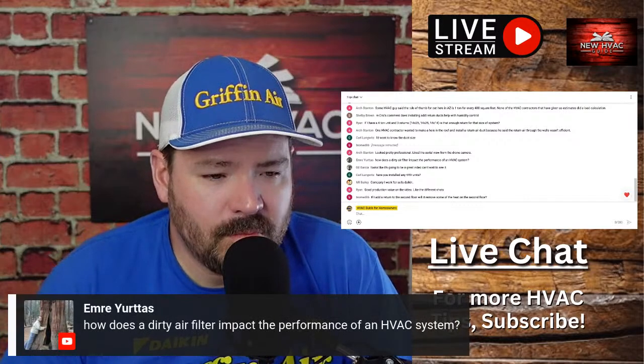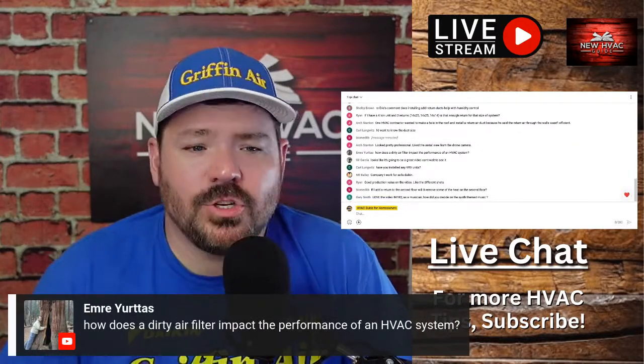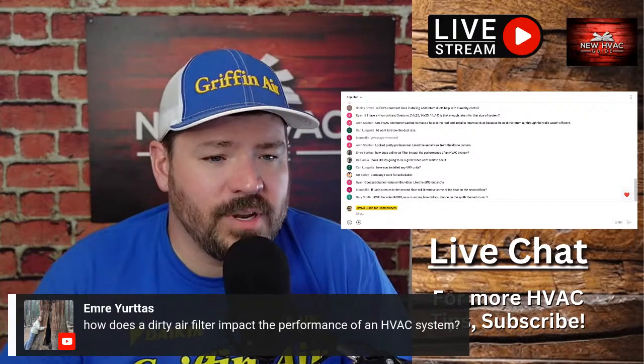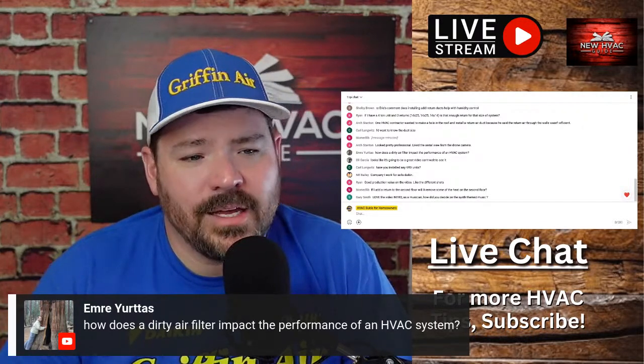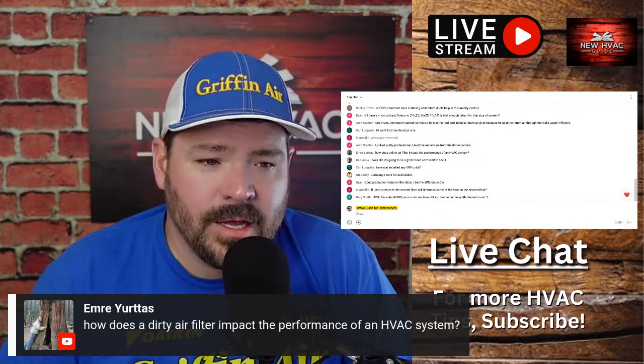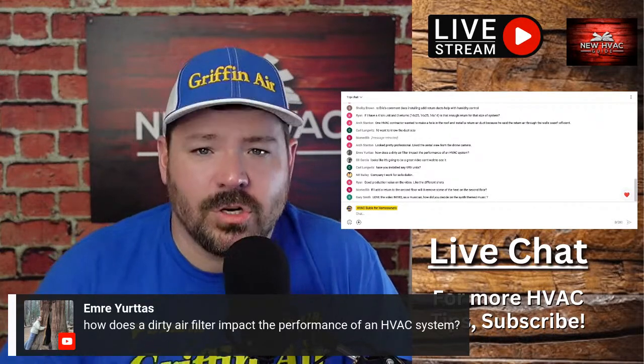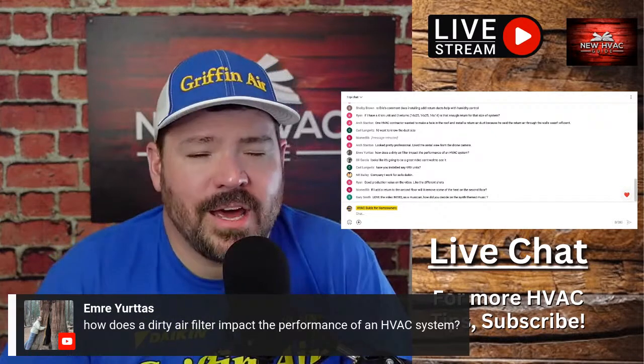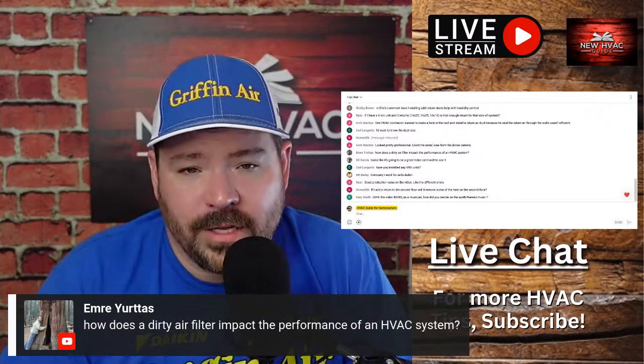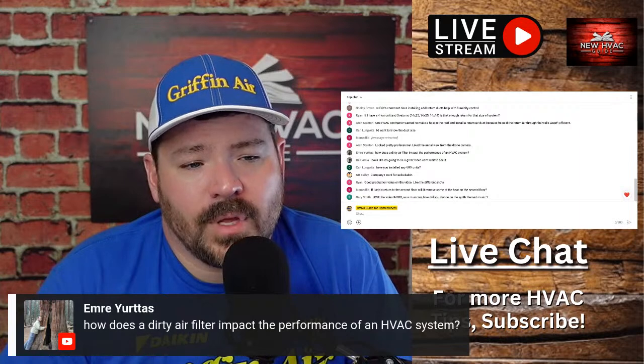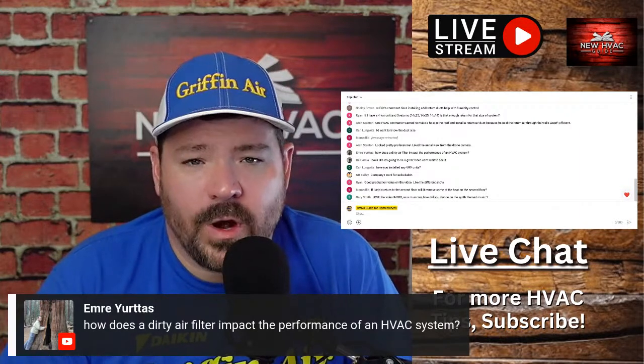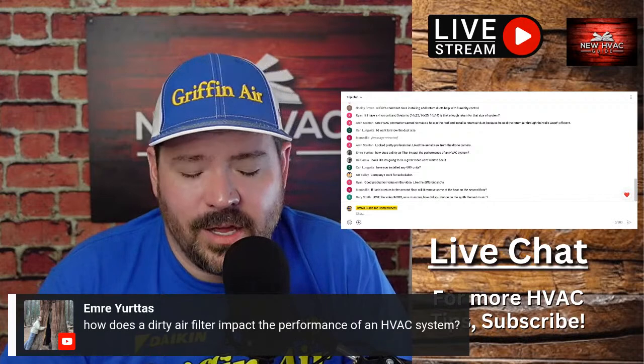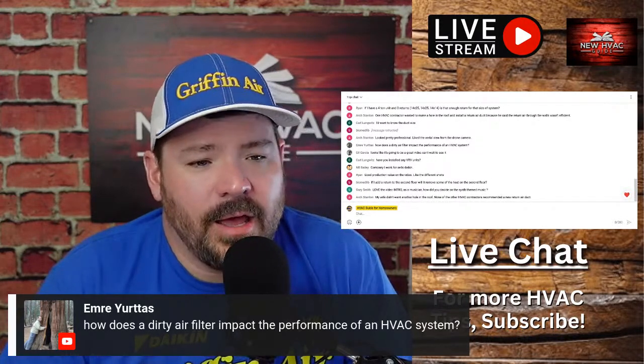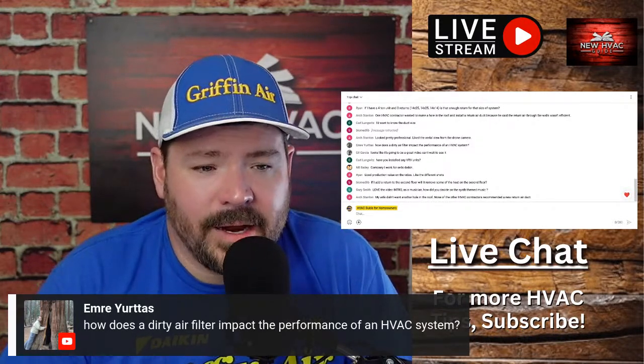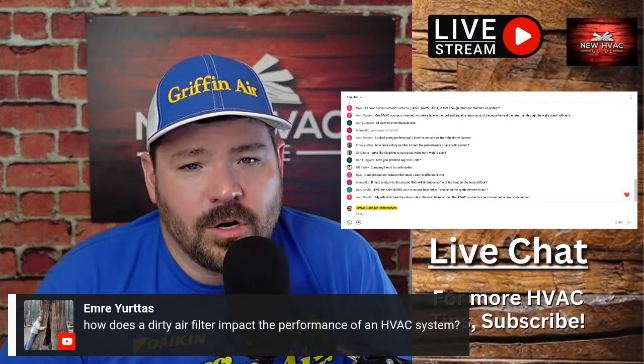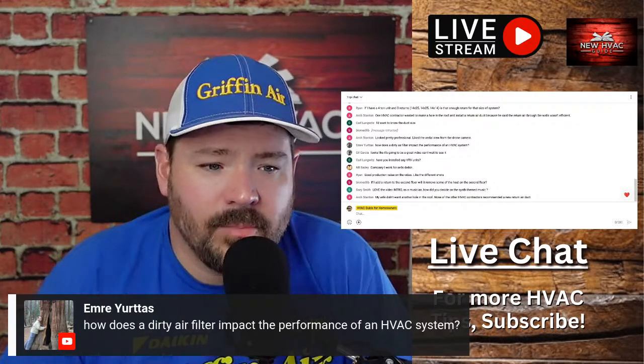Emery says, how does a dirty air filter impact the performance of an HVAC system? The main thing it does, Emery, is it slows down air, and that system is designed to have a certain amount of air pushed across that evaporator coil, among other things, and that's the main thing it does. But it does put more wear and tear on the indoor fan motor if it's dirty, and adds static and so on. But if you're not getting enough air across that evaporator coil, it could ice up, and you could have other issues as well.